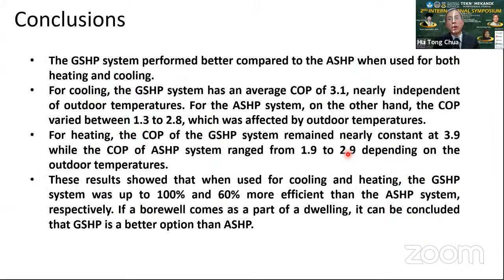So in conclusion, the ground source heat pump system certainly performed a lot better compared with the air source heat pump in both the heating and cooling mode. The ground source heat pump has an average COP of 3.1 for cooling, and for heating the COP is 3.9, which is very nice, because this certainly confirms that we have tracked steady state data, because the difference between the cooling and heating is about 1, which is what the thermodynamics will dictate.